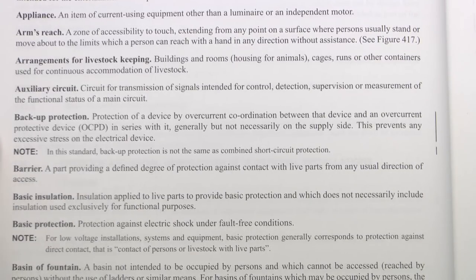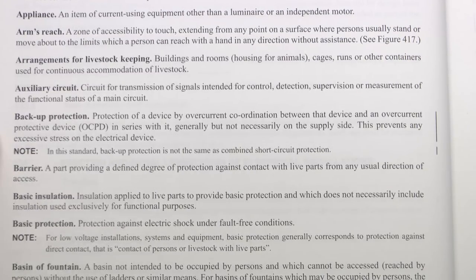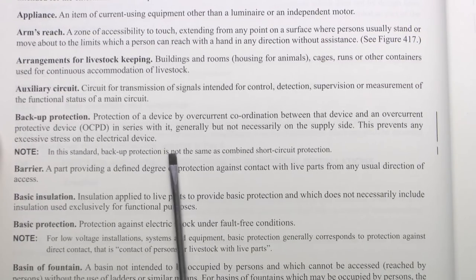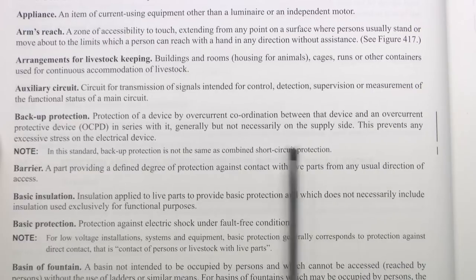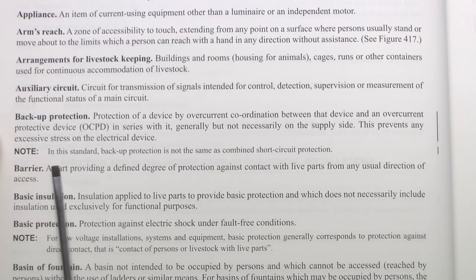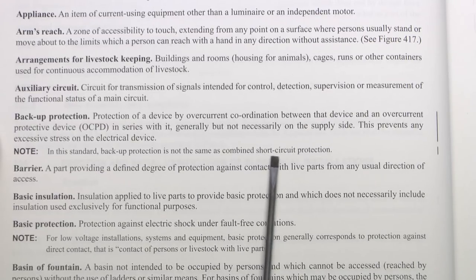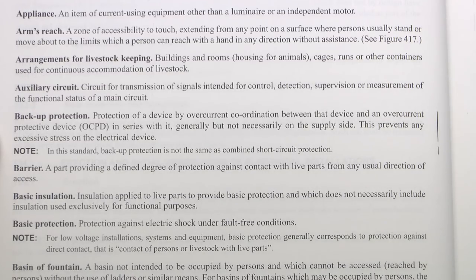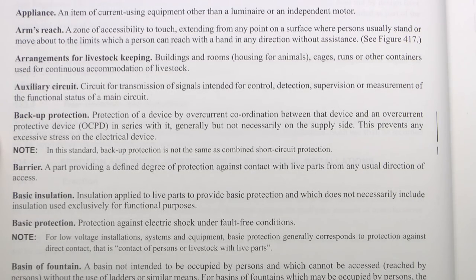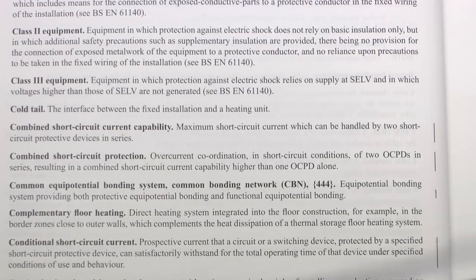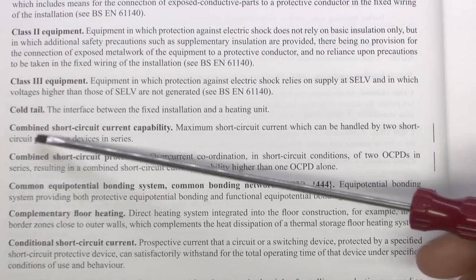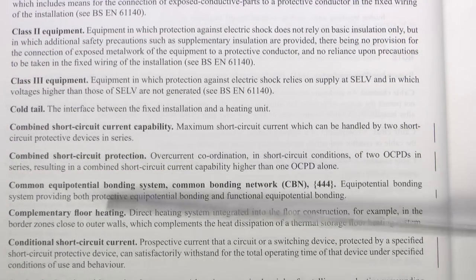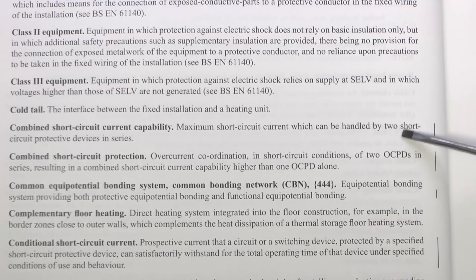First of all we have Backup Protection, which says: the Protection of a Device by Overcurrent Coordination between that device and an Overcurrent Protective Device, or OCPD, in series with it — generally but not necessarily on the supply side. And there's a note which has also been added: in the standard, Backup Protection is not the same as Combined Short Circuit Protection. We also have Combined Short Circuit Current Capability, which is the maximum short circuit current which can be handled by two short circuit protective devices in series — typically two circuit breakers, or two fuses, or something similar.